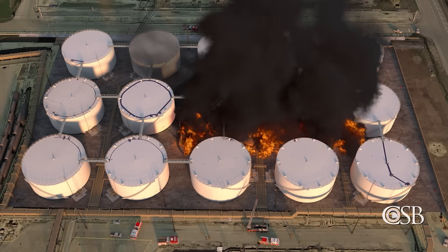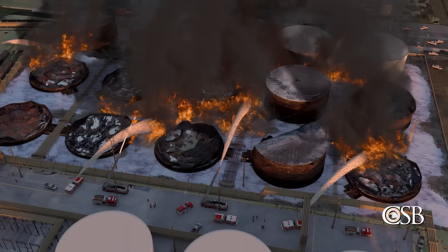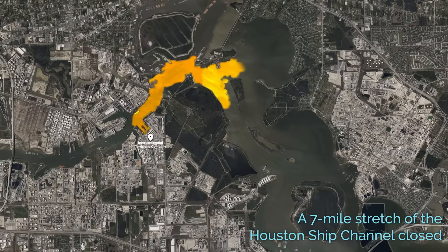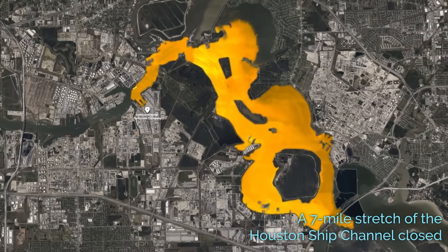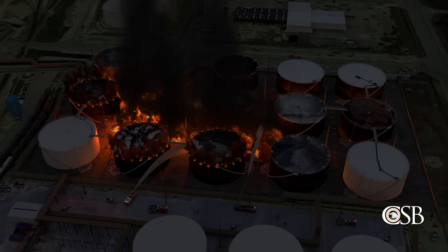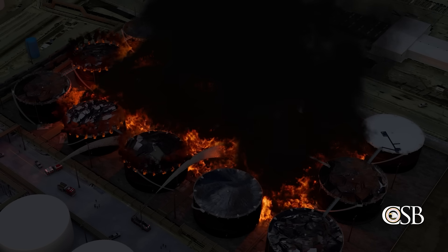As a result, hydrocarbon and petrochemical products, firefighting foam, and contaminated water accumulated within the tank farm and ultimately breached the facility's secondary containment wall, causing massive contamination of local waterways. The CSB notes that while NFPA 30 defines minimum requirements for tank farm design and spacing, other voluntary industry guidance documents by FM Global and the American Petroleum Institute provide more robust tank farm design criteria.